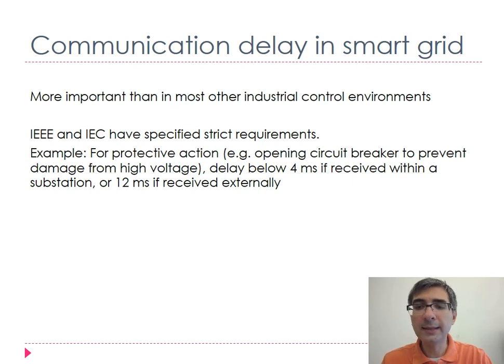It will start delaying the very important actuation needed for protective action - opening the circuit breaker to prevent damage from high voltage. If that happens too late, the power grid might fall out of sync and we might have an outage. So communication delay plays a very important role in the smart grid.